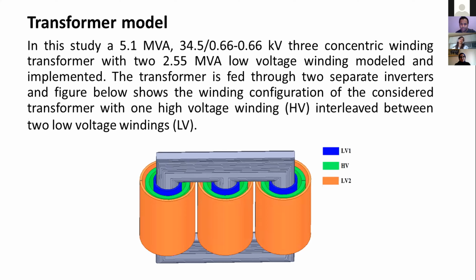Here, I would like to talk about our transformer model. In our study, a 5.1 MVA, 34.5 kilovolt to 0.66 kilovolt, three concentric winding transformer with two 2.55 MVA low voltage windings was modeled and implemented. The transformer is fed through two separate inverters, and as you can see in the figure, the winding configuration of the considered transformer is shown with one high voltage winding, in green color, interleaved between two low voltage windings.